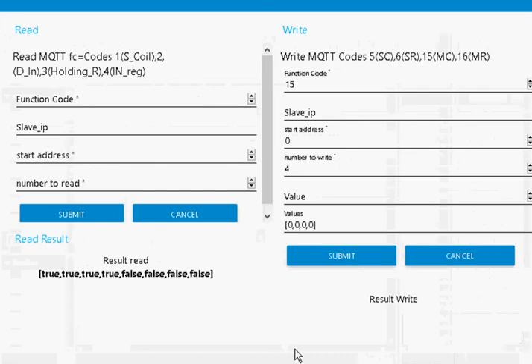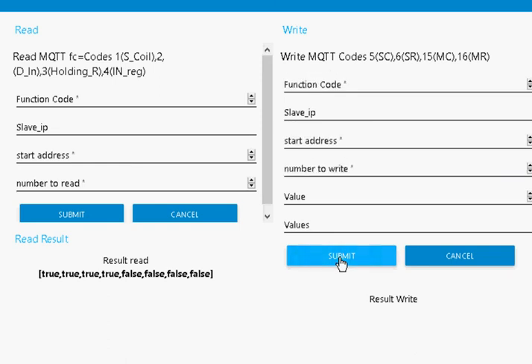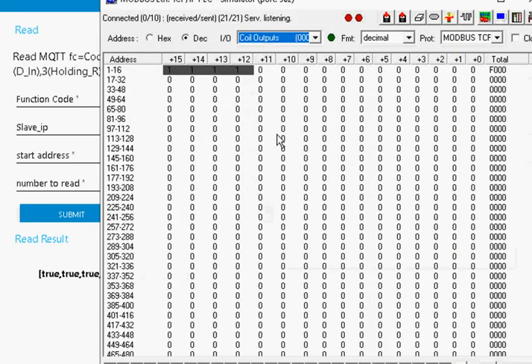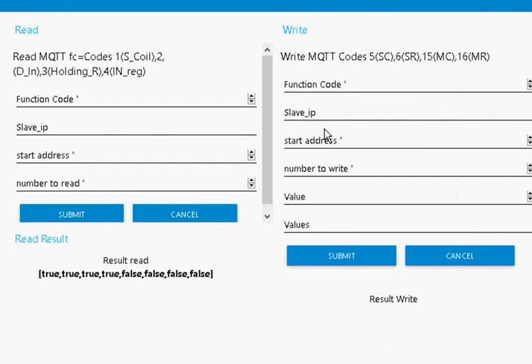So let's see it working. I'm going to overwrite these values here and set them all to false. I'm going to use function code 15 to write multiple coils, start at zero, number to use is four, and these are the values there. I'm just going to submit it. Now if I look at it, nothing's happened. You find this happens sometimes with this flow. There's no error correction in this, and there's no error detection. So what happens if there's an error on the Modbus write or the Modbus read? Well, you have to do it again.